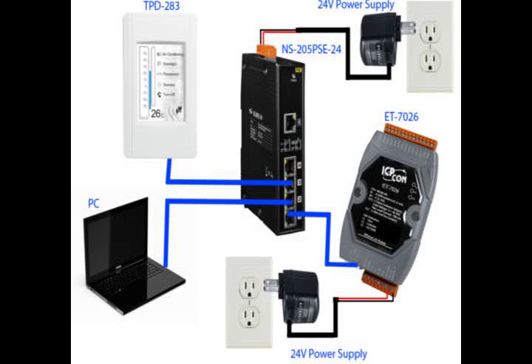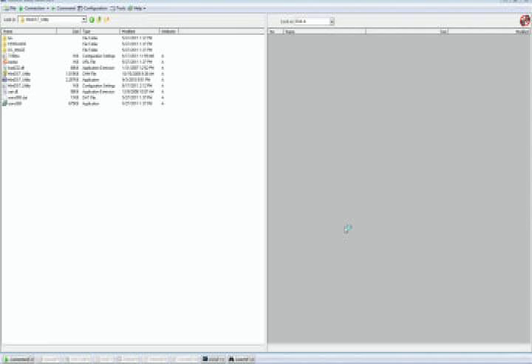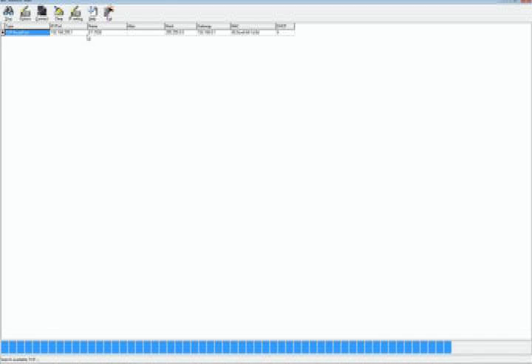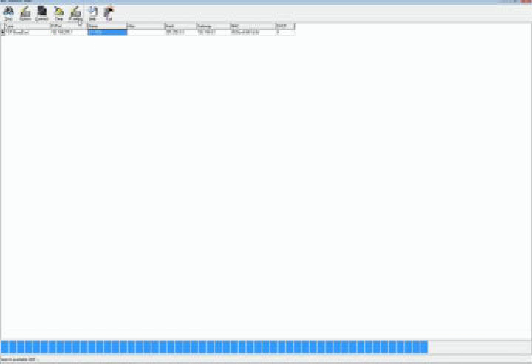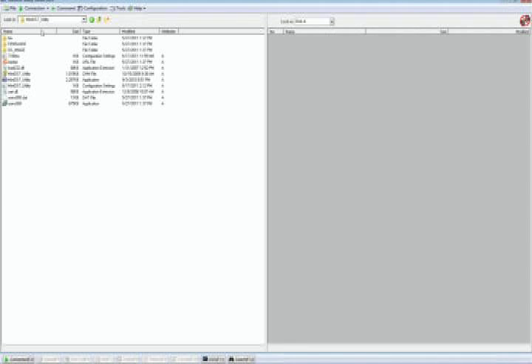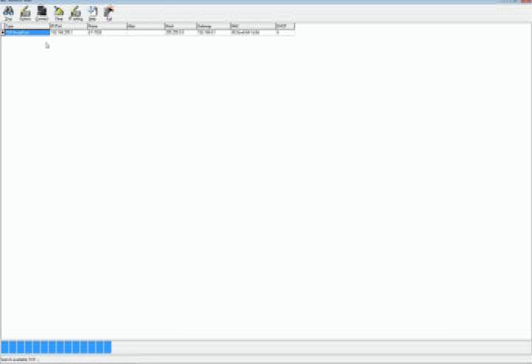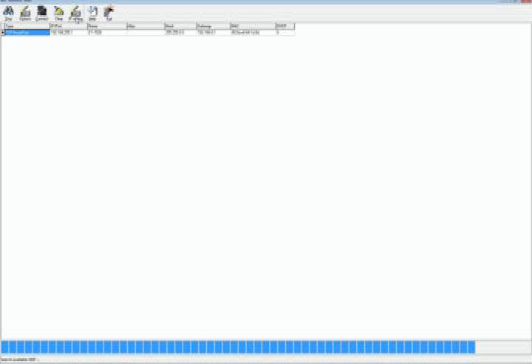You can use a free software ICP-DAS provides called MiniOS7 Utility to easily set its IP address. Download the software and install it on your computer. Then run the MiniOS7 Utility. Click the black downward-facing arrow and select Search. The utility will find the module. Select it and then click IP setting.